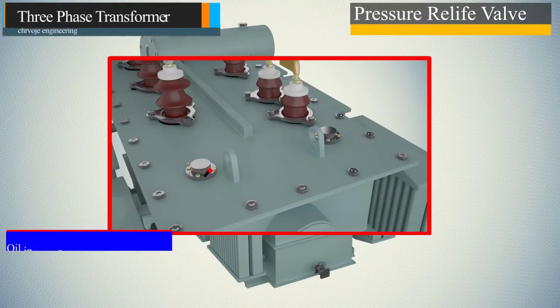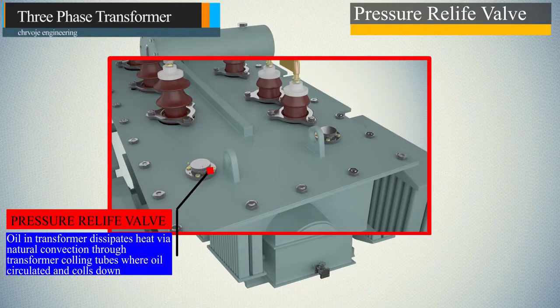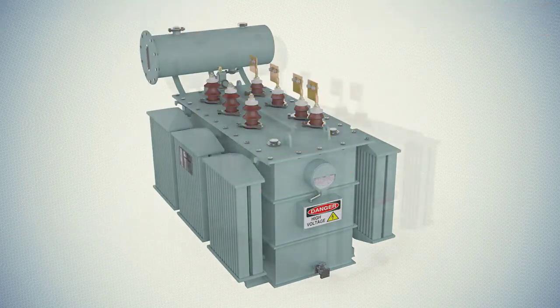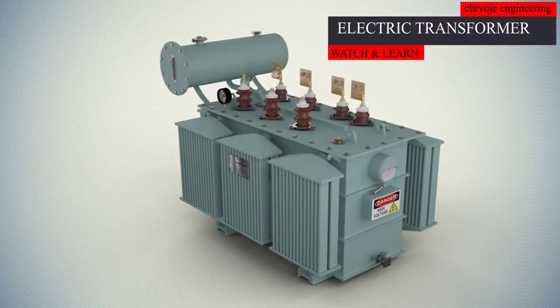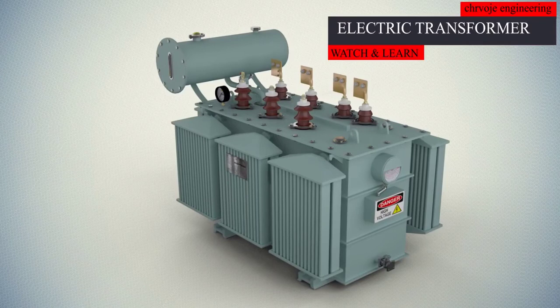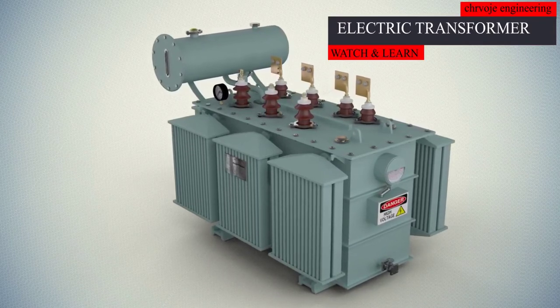The purpose of pressure relief valve is to relieve the internal tank pressure. When a transformer develops an internal fault or some other condition like high heat or partial discharging, the internal pressure can cause a tank rupture. A pressure relief device will open when the internal pressure exceeds the valve spring force. This allows the tank pressure to vent to the atmosphere. There are also various measuring devices on the transformer that measures temperature and pressure inside the transformer.